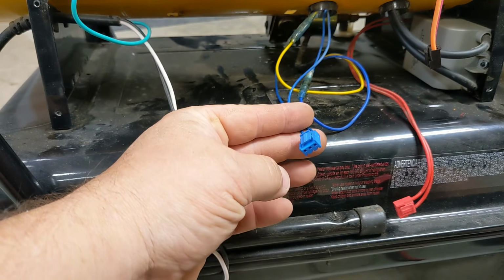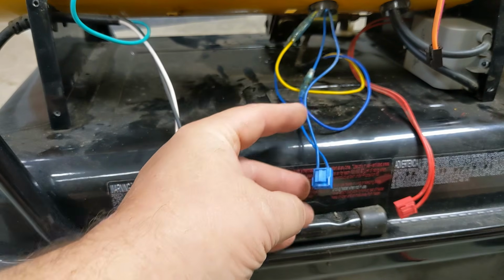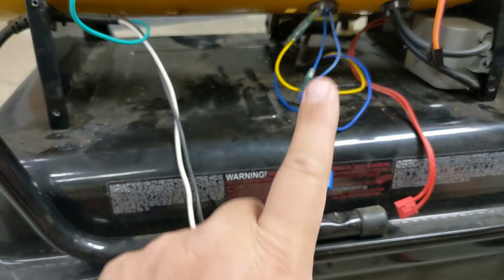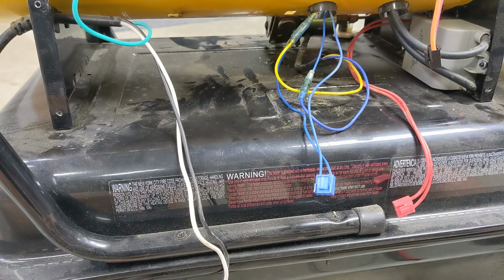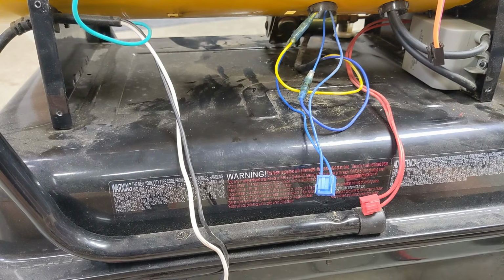So this is ready for a switch to be installed. This would be another relay on the board that would basically flip a switch to send juice to the fuel pump. Send power to the fuel pump, assuming that the thermal probe is not tripped. It's normally closed, which means it's normally connected, and if it gets too hot, then it breaks that circuit. So whether the board broke the circuit or the sensor broke the circuit, one way or the other, you would be cutting power to the fuel pump. So we got that under control. Last thing is the igniter. That needs to get 110.